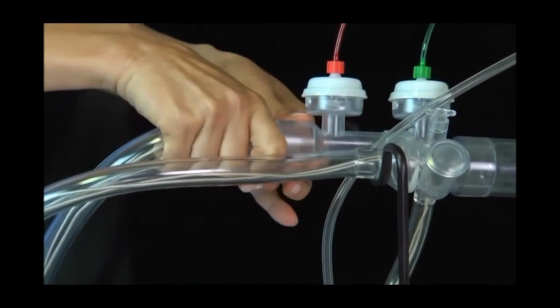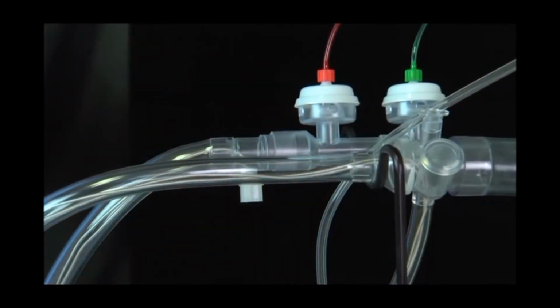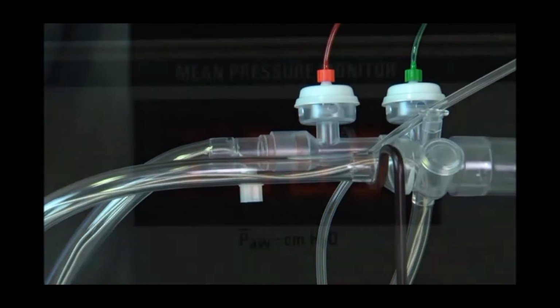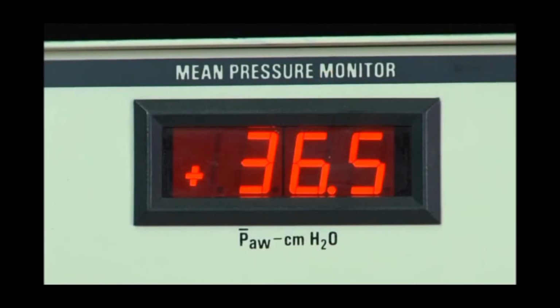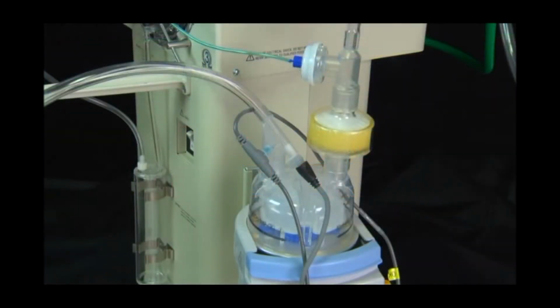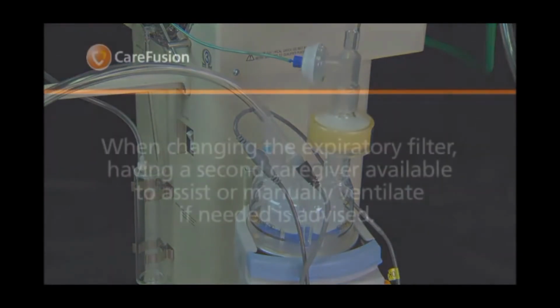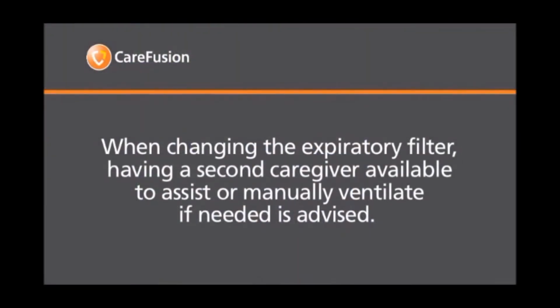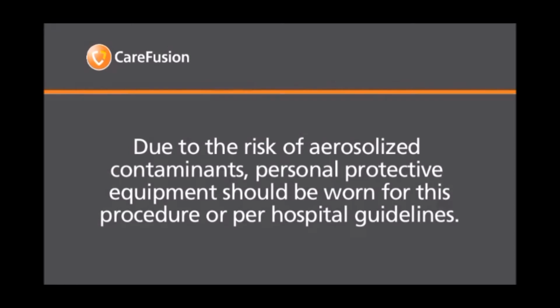The expiratory filter needs to be changed every 24 hours to ensure safe operation. It may also need to be changed if the pressures rise due to secretions. The inspiratory filter does not need to be routinely changed. When changing the expiratory filter, having a second caregiver available to assist or manually ventilate if needed is advised. Due to risk of aerosolized contaminants, personal protective equipment such as gown, gloves, masks, etc. should be worn for this procedure or per hospital guidelines.